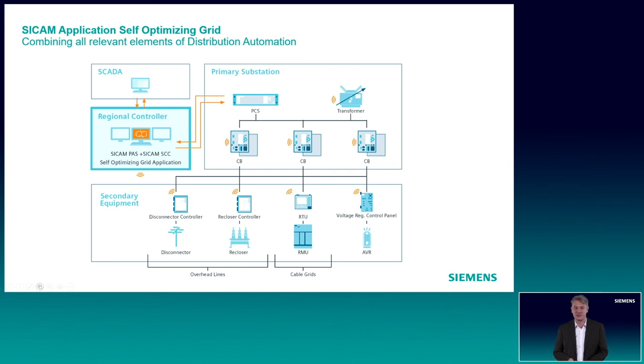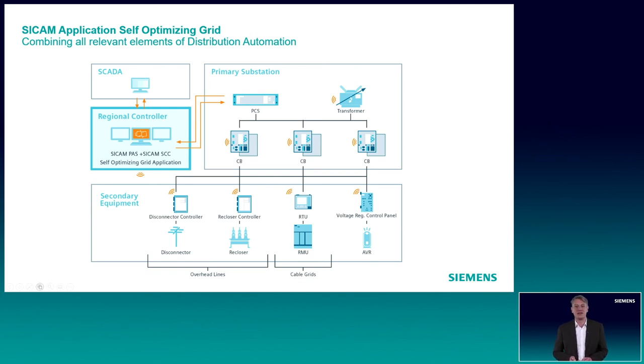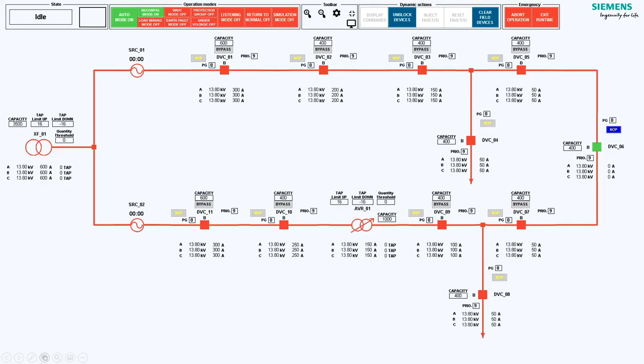Here you see the architecture of the self-optimizing grid, positioned between field devices and secondary stations, at the primary substation level and below the SCADA level. It connects all relevant data from the different levels and integrates the application. You also see the HMI of the SICAM SCC. The application shows a simple ring configuration with a transformer on the left-hand side, two infeed stations, and a simple ring. On the top bar is the operational panel showing the different functions which can be enabled, disabled, or monitored. In idle state, all relevant data are processed in the SICAM PAS, which takes a monitoring view of the total grid.